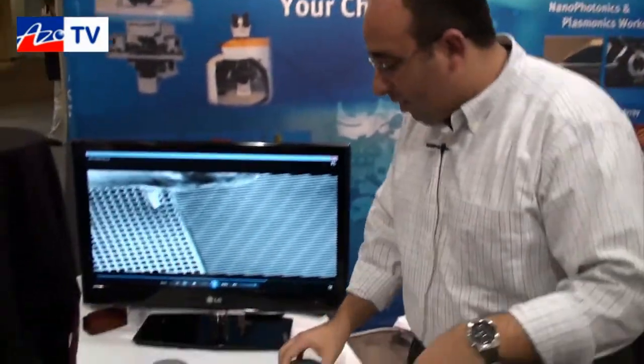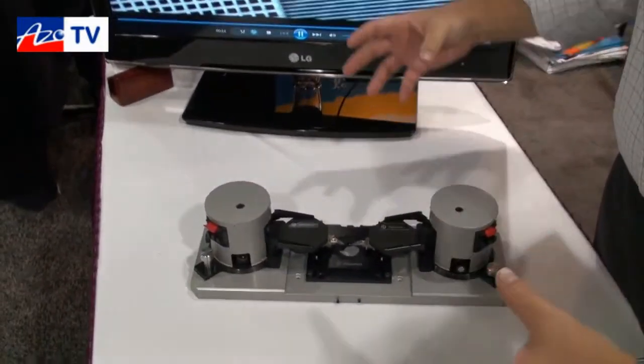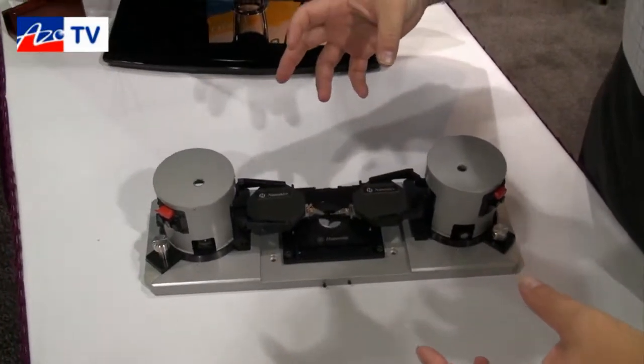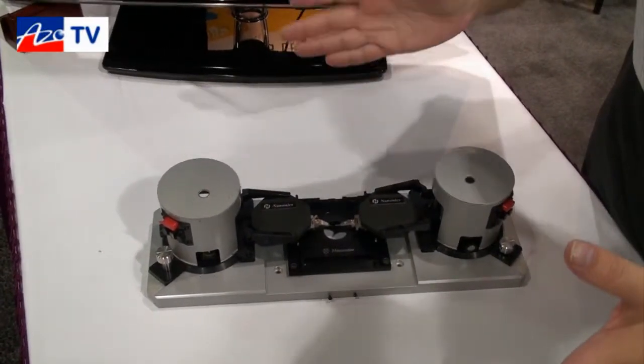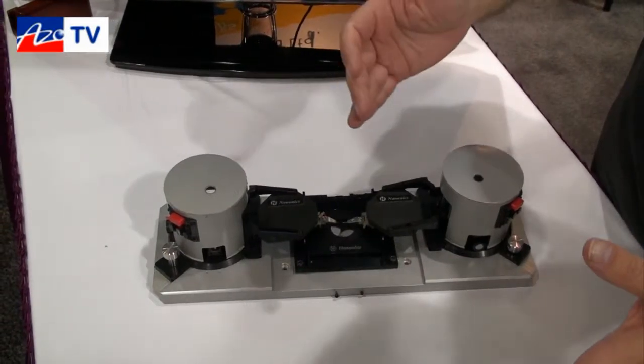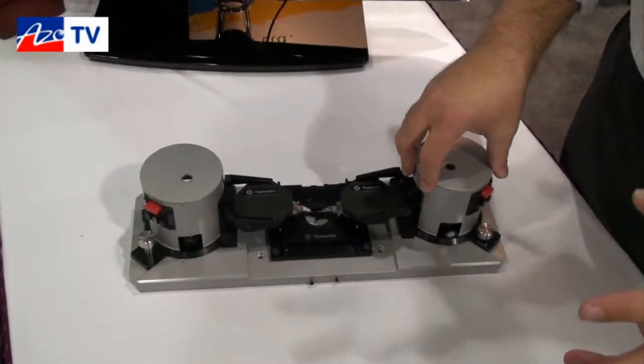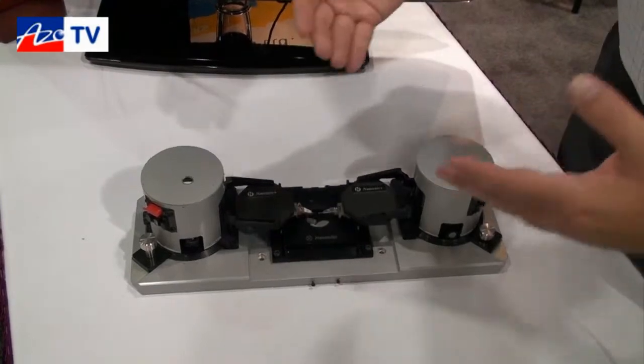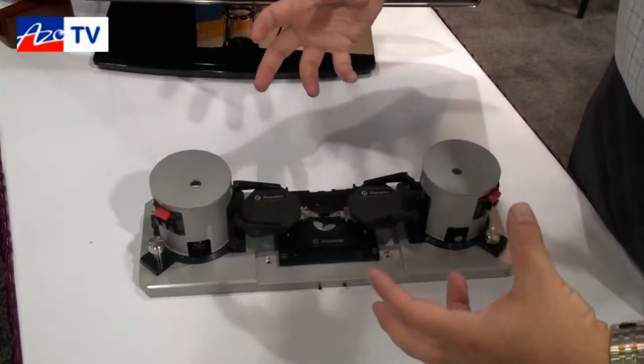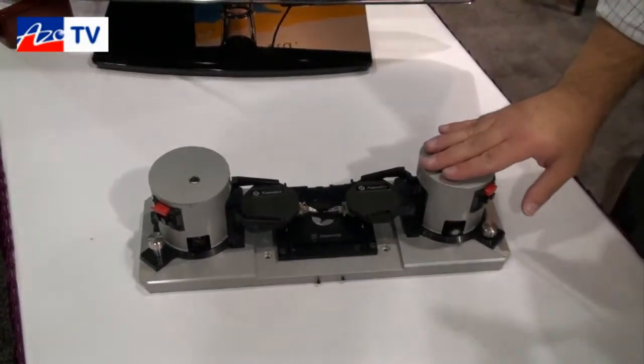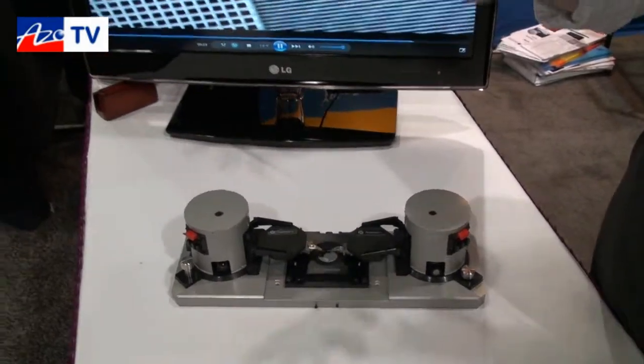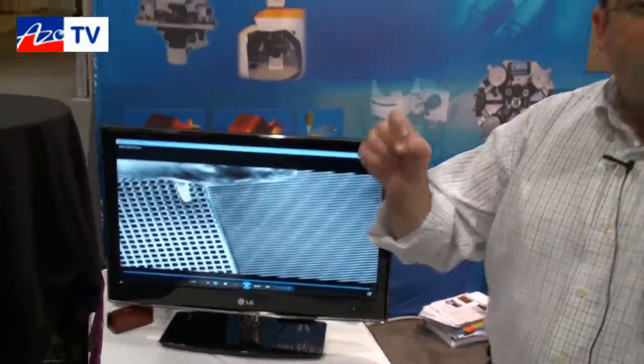So with this system, with this configuration, we can bring up to 4 independent probes. So each probe works independently. You have AFM feedback, you have AFM scanning. Each one can be removed and used as an independent AFM. Each one has tip and sample scanning, and we can have up to 4 of them working together. One popular area for more than 2 probes is when we do multi-probe electrical measurements. So you have 2 probes creating electrical contacts, and you have a 3rd probe scanning over the area to get electrical conductivity or resistance measurements. So that's the typical sort of configuration.